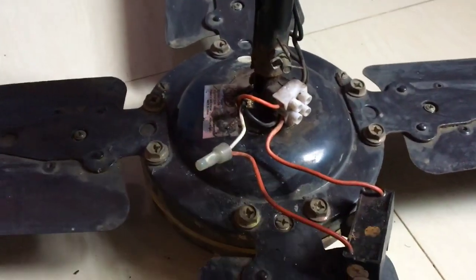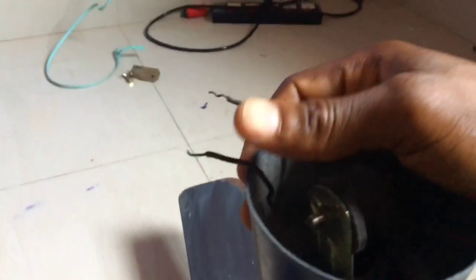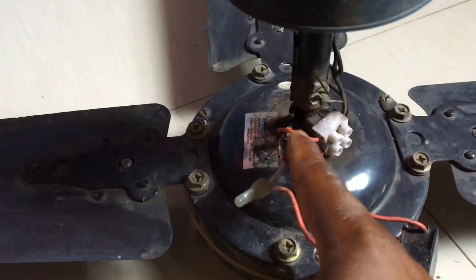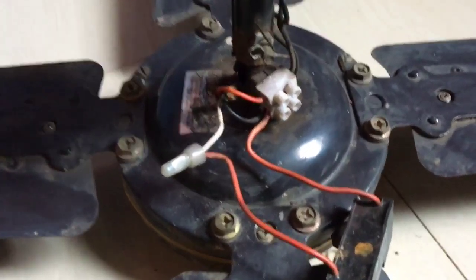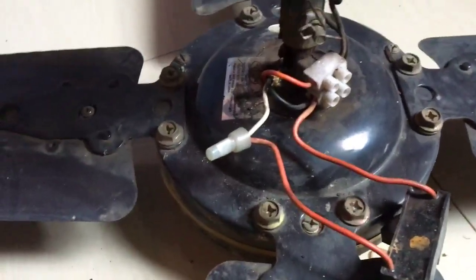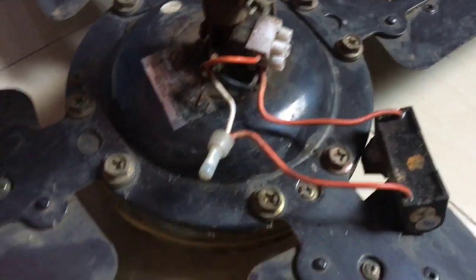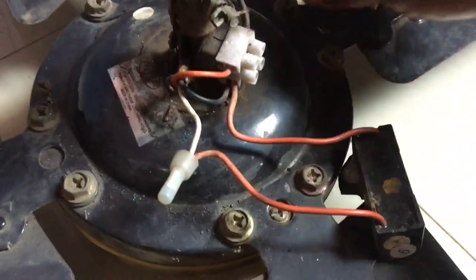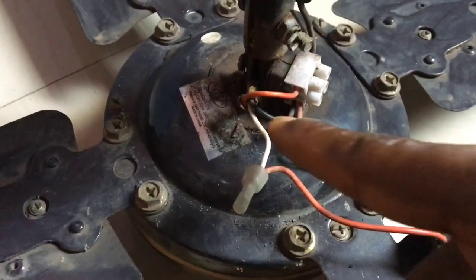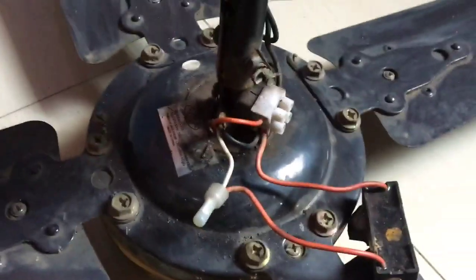Okay, but before you do this, I recommend that you detach it completely from the supply. If you detach completely from the supply, when the electric motor is in order, all these three terminals will read continuity with your digital multimeter. Set it to continuity. The three wires coming from the electric motor will read continuity. So if any of them is not reading continuity, know that your electric motor is bad. Then if it has earth leakage, meaning you are reading continuity between a terminal and the body of this material, if you see any continuity reading from any of these terminals and the body of the fan itself, just know that your coil is bad.